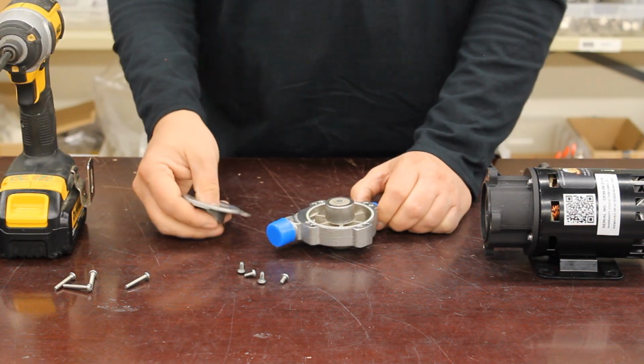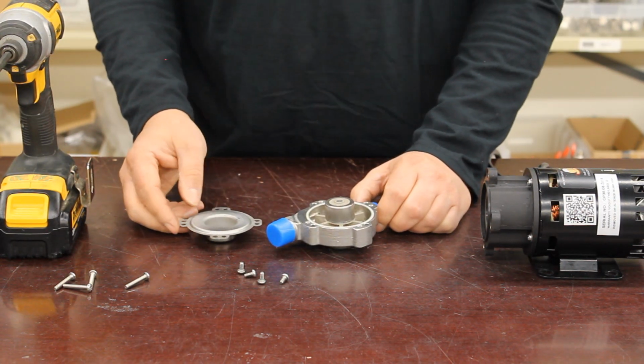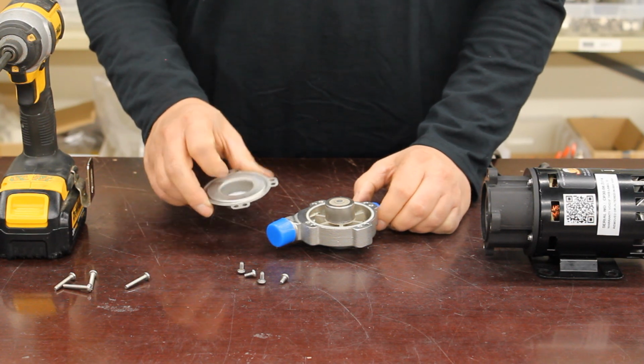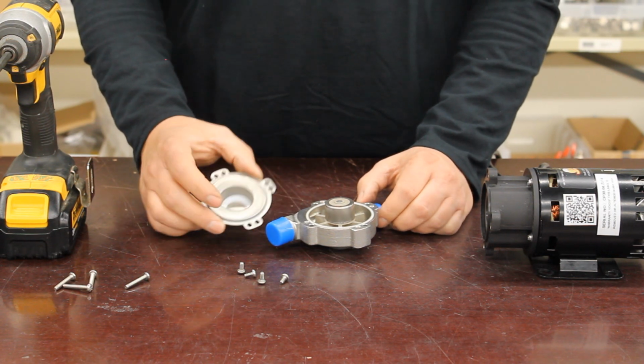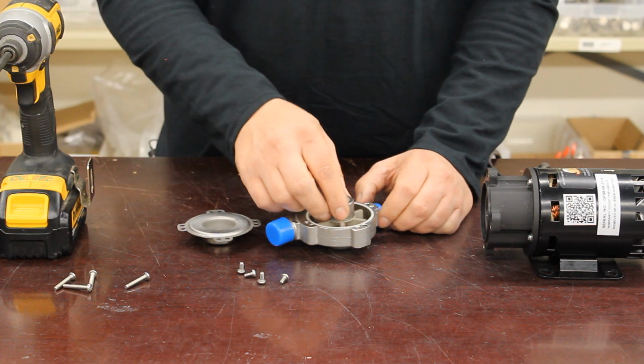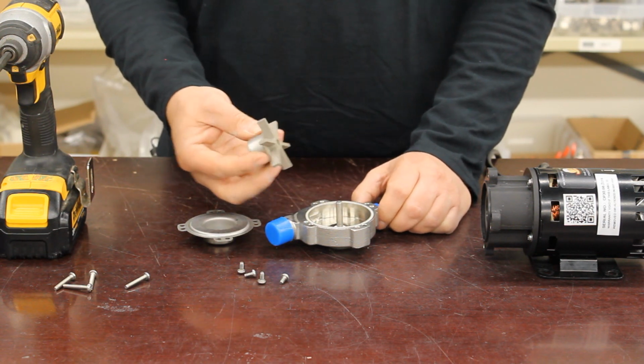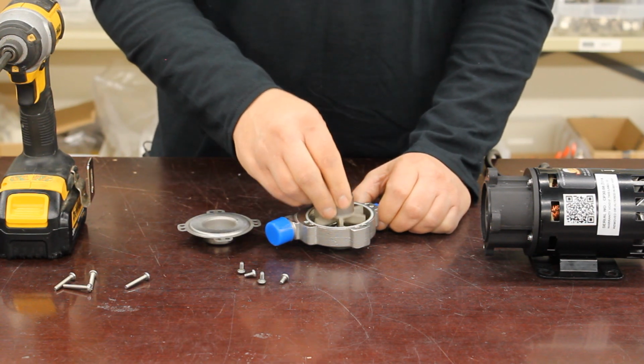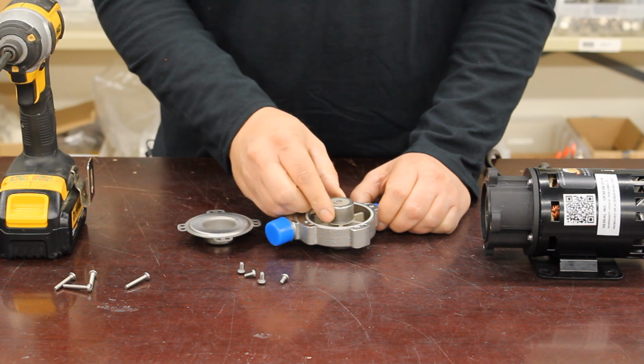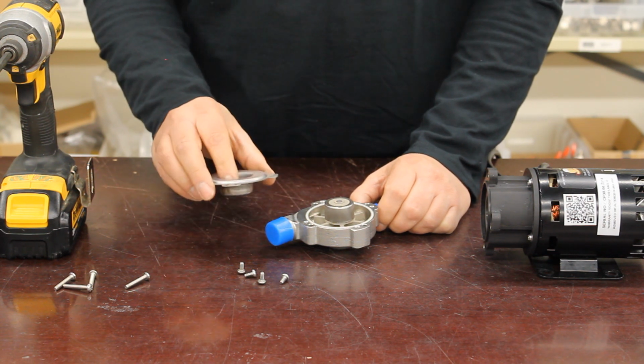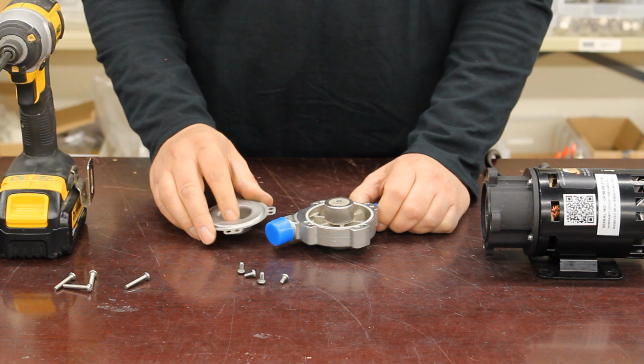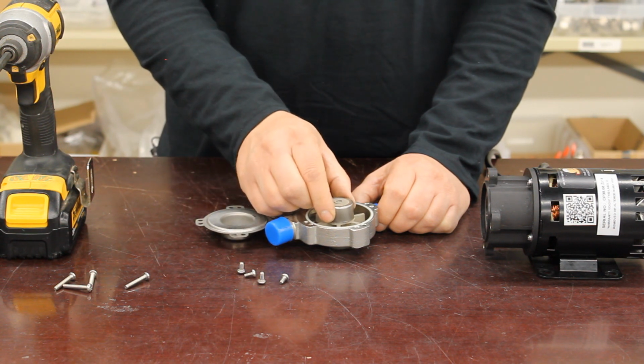Now, most of these interior components can be replaced if they do wear out. In some older pumps, you will see some wear on the thrust washers. Those are bearing surfaces, so they will wear out. If you've got issues with the head making a rattling sound often, it's most likely because the thrust washers are being worn down and there's too much play in the head.